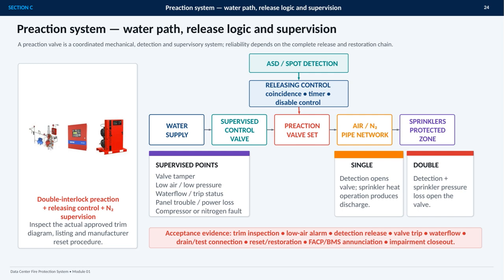Trim inspection, low air alarm, detection release, valve trip, water flow, drain or test connection, reset and restoration, FACP or BMS annunciation, and impairment closeout. Always verify the actual approved trim diagram, listing, and manufacturer reset procedure before testing or restoring the system.